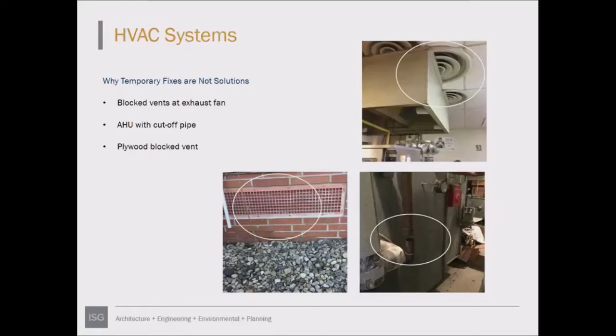For HVAC systems, figure out when it was last commissioned, or whether it needs recommissioning. Recommissioning or commissioning a system is very important - everyone can install all their equipment, but unless it runs correctly, it's not going to perform well. The upper right photograph shows some older equipment, probably installed in the 50s or 60s, so it's 60 to 70 years old. Can it meet today's ASHRAE standards? I very much doubt it.